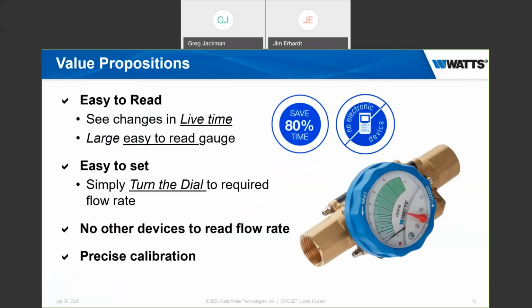So what is it about the iDROSET that is going to help you get off the job more quickly? First of all, it's easy to read. You're not going to have to attach an instrument to see what the flow is. The flow will be live time, meaning as long as the pump is running, as long as there's flow through the system, the needle will be indicating it. It's obviously an easy to read gauge. It's easy to set. There's no tools involved. You just simply turn the hand wheel to get your required flow.